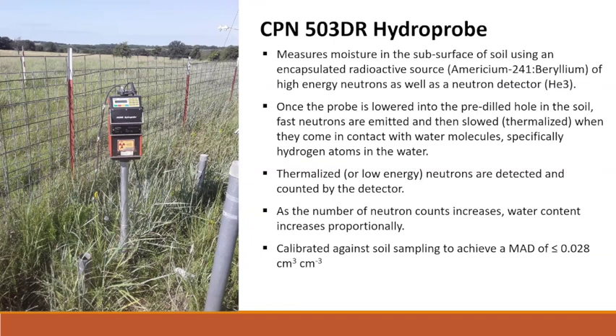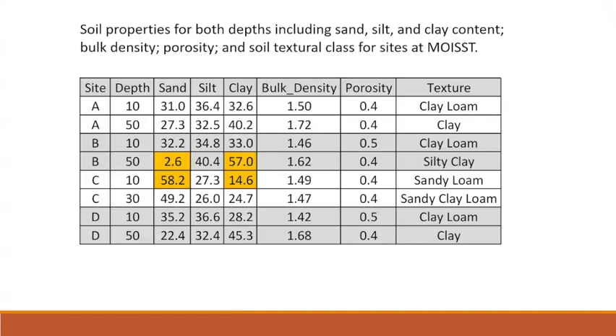But you take that off, put this probe on it, and there's a little latch here, and little increments that you drop the source down at, whatever increments you've set, so 10, 30, 50, 70 centimeters. Once you drop the probe down, it sends off neutrons. They're thermalized by the water molecules, the hydrogen, and they're counted by the detector. As the water content goes up, you count more. They're calibrated against the soil sampling to achieve the MAD of less than or equal to 0.028. And that was with our soil sampling.